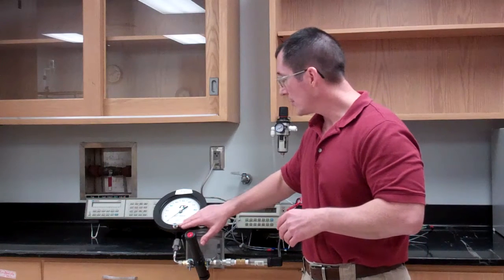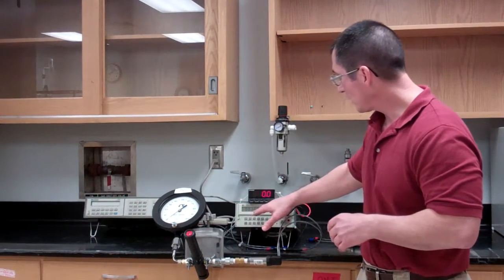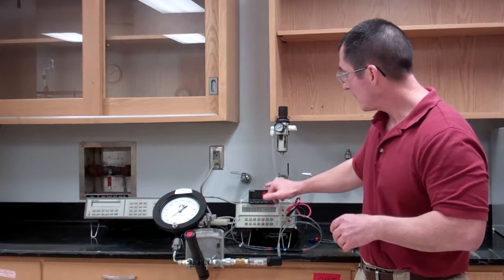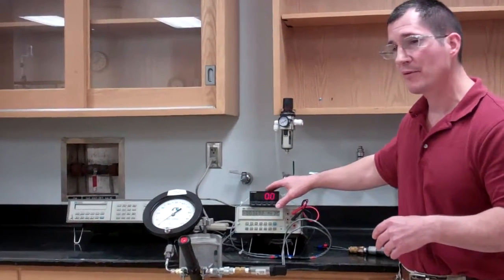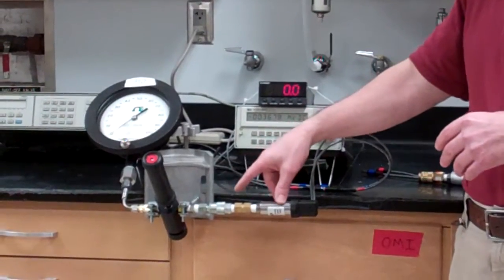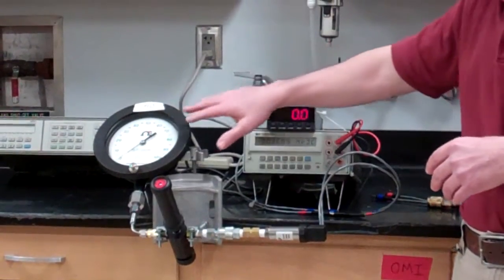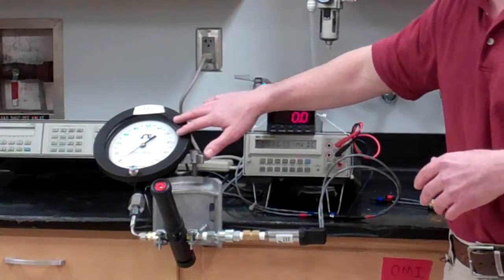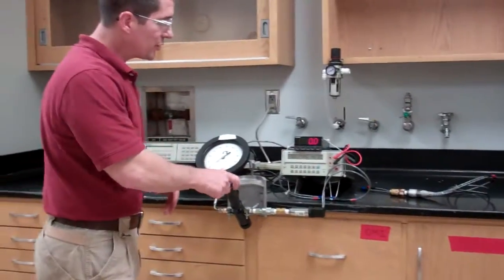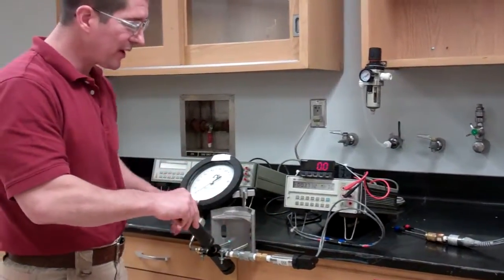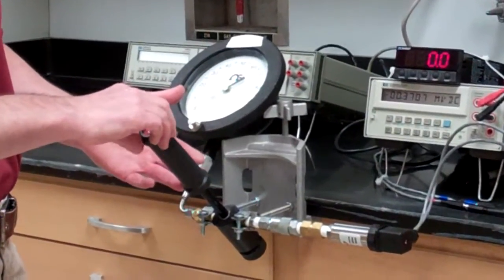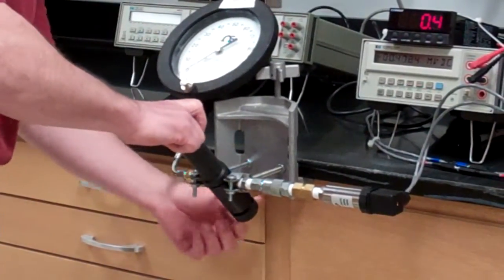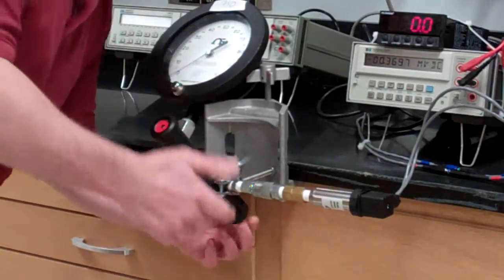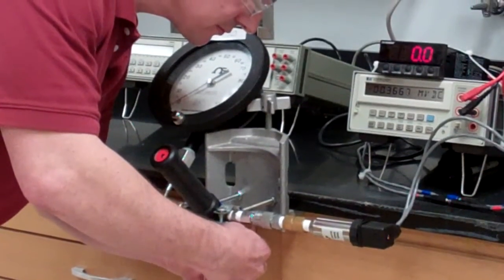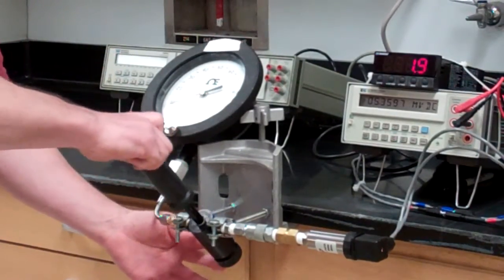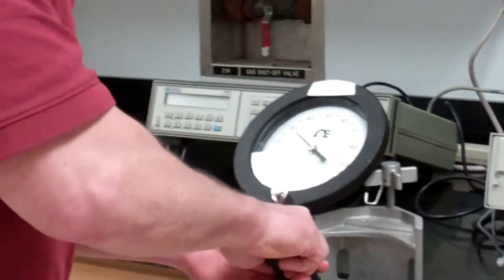And so what we're going to do is we're going to apply a pressure, and then we'll be able to read the output from the transducer. And we also have a meter that does two things for us. One thing is it provides an excitation power supply to our transducer. And it also gives us a display reading that should pretty well match what the gauge gives us. Now, to put pressure on this transducer, we have to use it kind of like a bicycle pump, a little bit fancier. Got to close the valve. There's a bleed valve here on the bottom. So once it's closed, you can pressurize it.